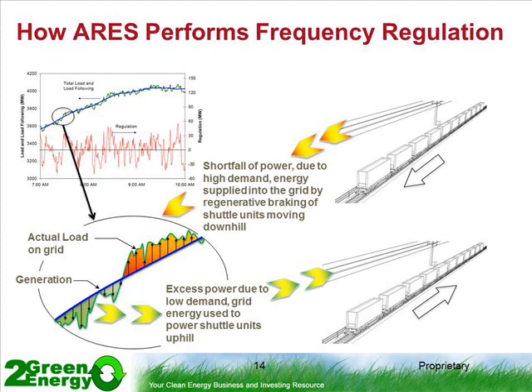It always reminds people of that game from childhood with steel balls hanging from cords—you pull the one out on the end, release it, and the one on the other end swings out. With ARES being used as a regulation or ancillary services machine, you see a bunch of ARES cars queued up mid-slope, and they start peeling off downhill when the system needs frequency or voltage support. If the grid becomes over-frequency or over-voltage, the cars on the other end start to move upslope. So you're constantly moving cars up and down, like an accordion, to maintain grid stability that would normally have been provided by a spinning turbine generator fueled by gas, oil, or coal.